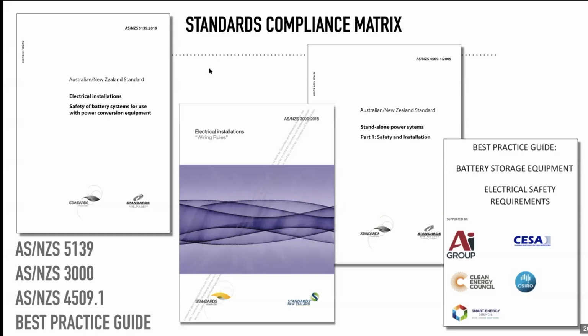It was put together because we lacked an actual product standard for battery systems in Australia and New Zealand. And in lieu of a product standard, we chose to collect together many methods of meeting a high level of safety. This document is co-authored by all those groups on the cover, and it is currently in version 1. Now, it's version locked to the standard, so 5139 references this document a lot, and I'll cover that in a second, and it's version 1 locked. So even if this document gets updated, it's still version 1 that we have to refer to.